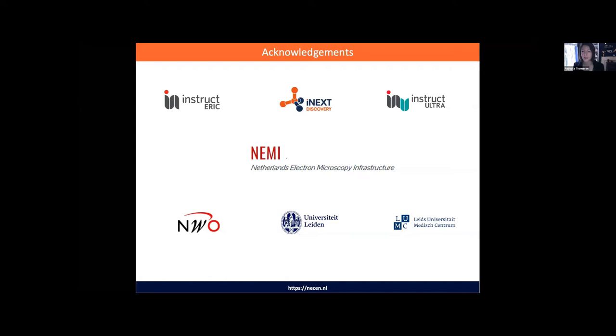The last question: do you use the phase plate for tomography, and if so how do you manage that over the course of the tomography collection? Yes, some users want to use phase plate, especially for tomography. In that case, most projects we will do tomography with phase plate during the day, but overnight we take it out and do a normal tomography session, because we don't find it stable enough to be confident it will be okay overnight. That's how we run it basically.